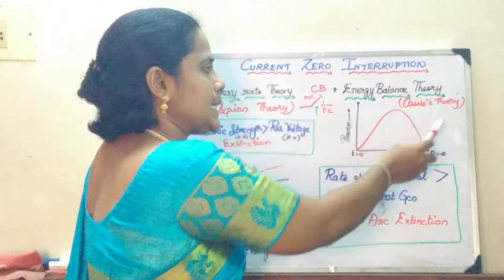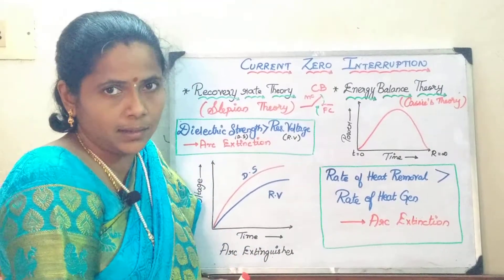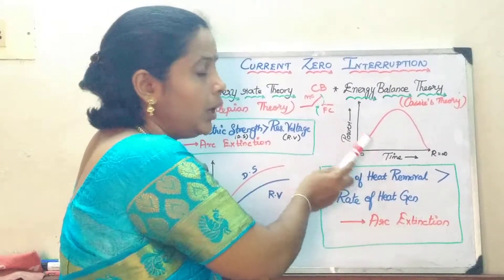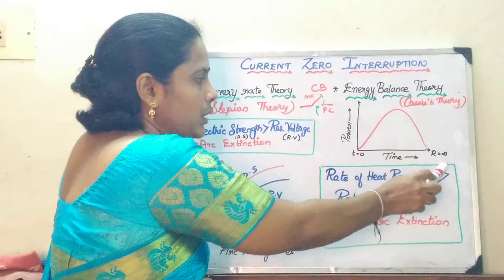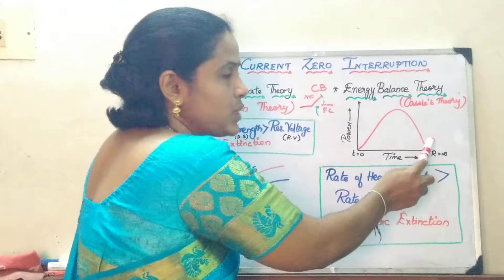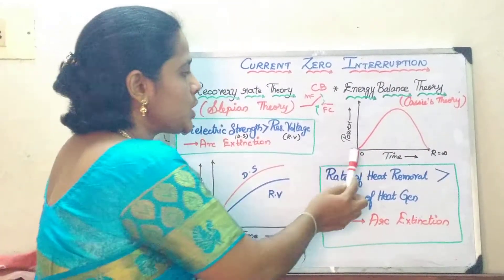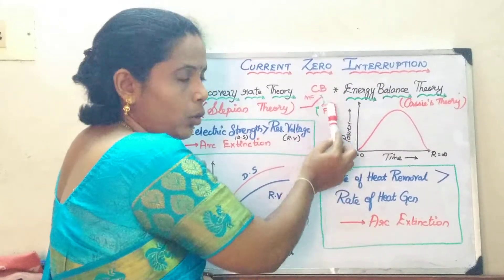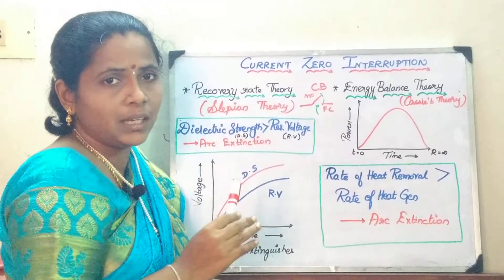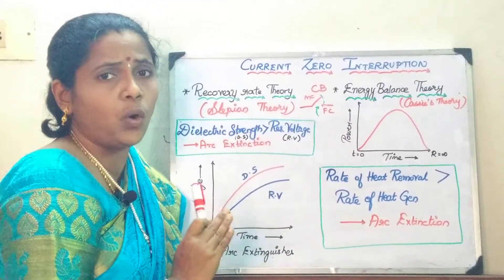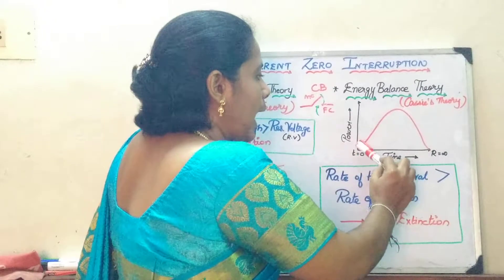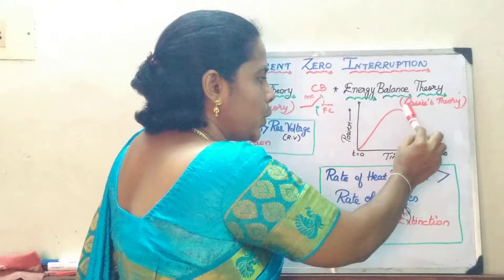Now we will move on to Cassie's theory, or the energy balance theory. This graph is plotted with respect to power versus time. It is not drawn with current versus time because the waveform gets quenched at every current zero — every half cycle you are going to quench the arc. Initially, at time T equal to zero, when the contacts are open, there will be some ionized gases, and the restriking voltage will be zero at this point. As time passes and the current and voltage increase, the power also increases, and when the current reaches zero, the power also reaches zero.